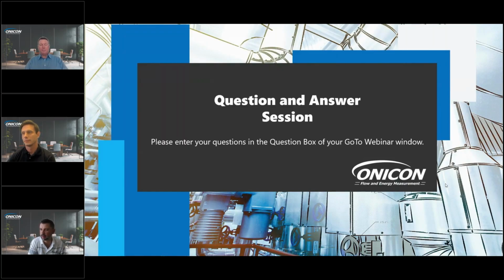Looks like it's based around our ONICON temperature sensors and how they're calibrated. I think Jacob did a good job talking about calibrated temperature sensors. And I think the key word there was matched temperature sensors, comparing us to just standard RTDs, which are typically not, even if they're calibrated, not matched together. So what ONICON does with our solid state temperature sensors is we take the two temperature sensors, and based on the application, it's going to be living in chilled water, hot water, condenser water. We put the two temperature sensors in the same bath, and we compare them to a NIST traceable master sensor.